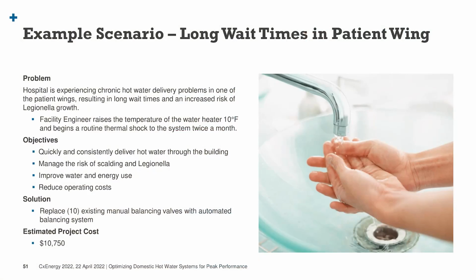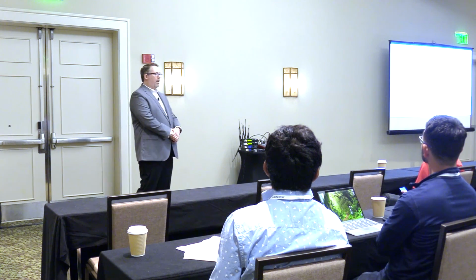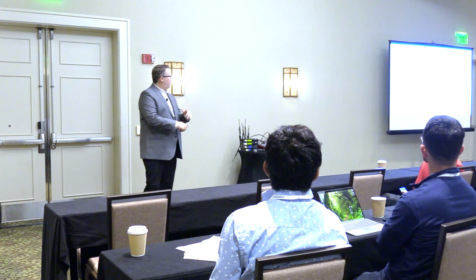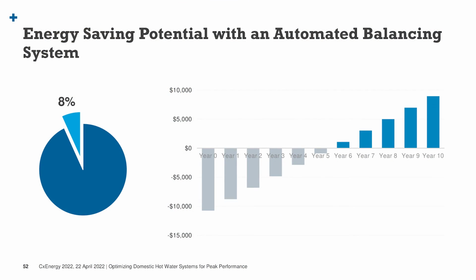Here's an example scenario: a hospital experiencing chronic hot water delivery issues in one of the patient wings, resulting in long wait times. The facility engineer increases the water heater temperature, hoping that helps, or maybe installs a larger pump, using more energy. The solution here was to replace 10 mixing or balancing valves, with an estimated installation cost of around $10,000. I put this together to give an example of the ROI on energy savings once they're able to consistently maintain those temperatures—they reduced the water heater temperature and realized energy savings that pay out over the course of a few years.